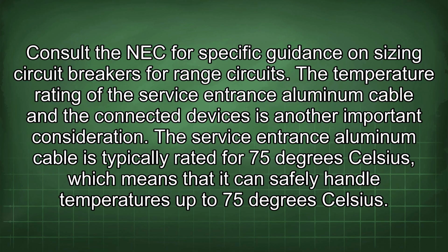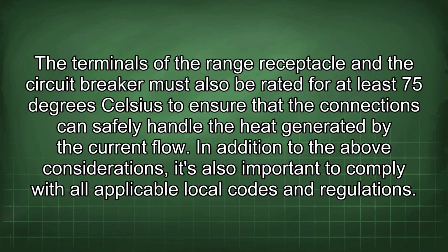The temperature rating of the service entrance aluminum cable and the connected devices is another important consideration. The service entrance aluminum cable is typically rated for 75 degrees Celsius, which means that it can safely handle temperatures up to 75 degrees Celsius. The terminals of the range receptacle and the circuit breaker must also be rated for at least 75 degrees Celsius to ensure that the connections can safely handle the heat generated by the current flow.